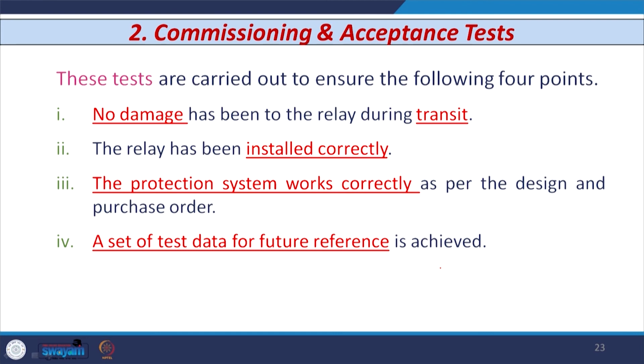The first is that there should not be any damage to the relay while it is in transit. I procure the relay, I have given the order to the manufacturer, who has manufactured a specific type of relay and performed all the type tests we have discussed, all seven or eight types of different tests. Finally, the relay passes all the tests and is sent by the manufacturer, and while it is in transit or transportation, there should not be any damage to the relay. To ensure that, we need to carry out the commissioning and acceptance test whenever we receive the relay. That is one thing.